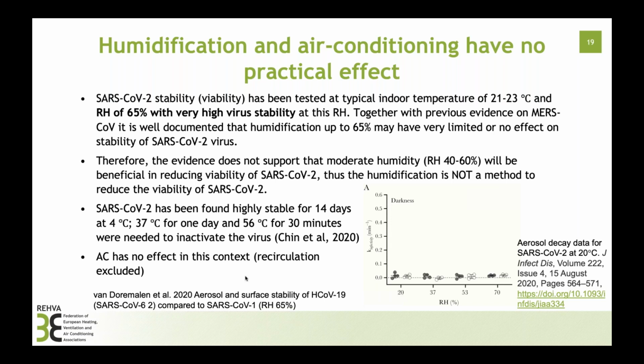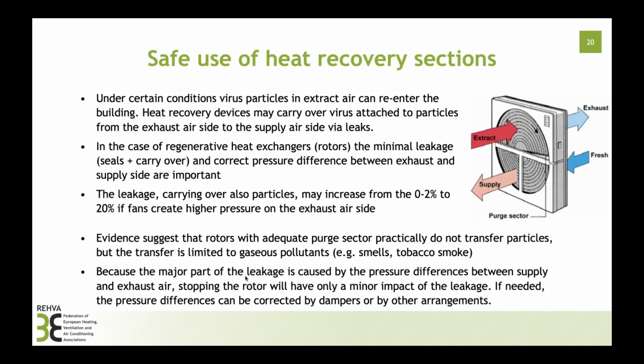So more than 80%, and it's like wet surfaces, wet cleaning will make a difference when you can really deactivate this virus, but it cannot be done with humidification. So humidification is not a method for this virus to reduce viability. And the same applies for the temperature. Temperature needs to be very high, so room temperature set point has no effect in this case. So basically everything that applies for heating, cooling, temperature, humidity, set points, there is no practical effect and no need to change these set points in epidemic conditions.